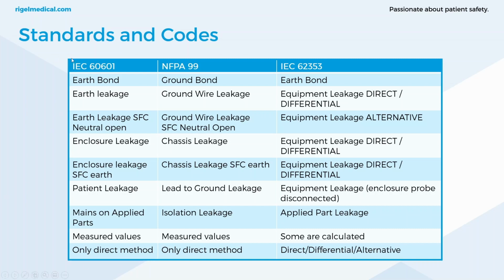Sometimes you get asked what the difference is between a standard and a code. Well, a standard is a document that has all the technical procedures. It gives guidance for manufacturers and any equipment users. It contains requirements, but the compliance can be voluntary. A code such as NFPA 99, now that has been enacted into law by the regional or national authorities, so that then an engineer, a biomed, is legally obliged to comply to that code. It contains mandatory requirements that are obligatory.